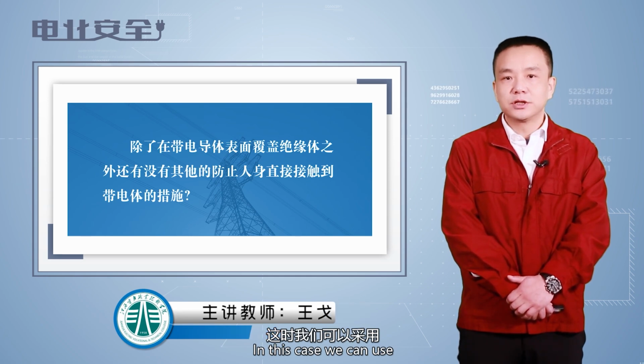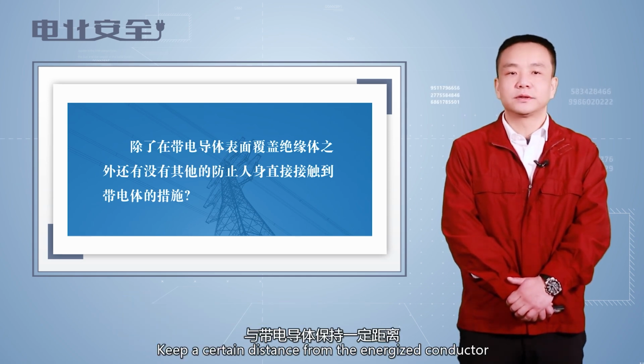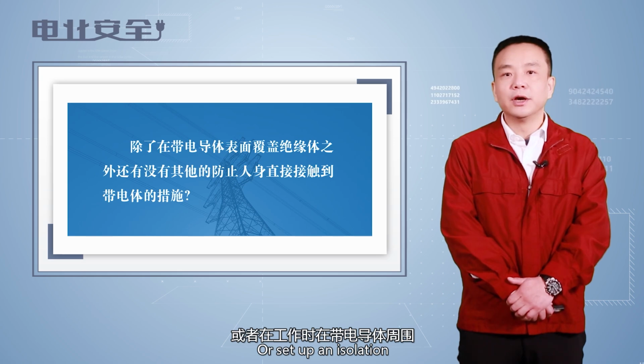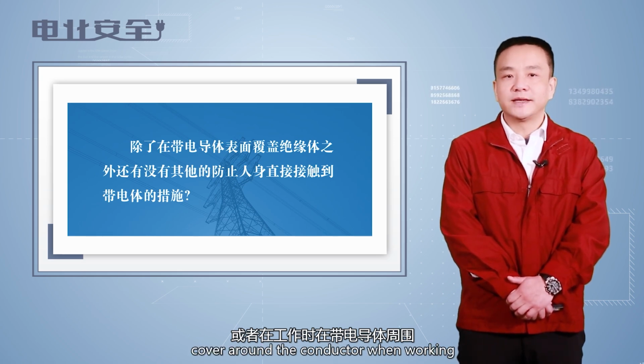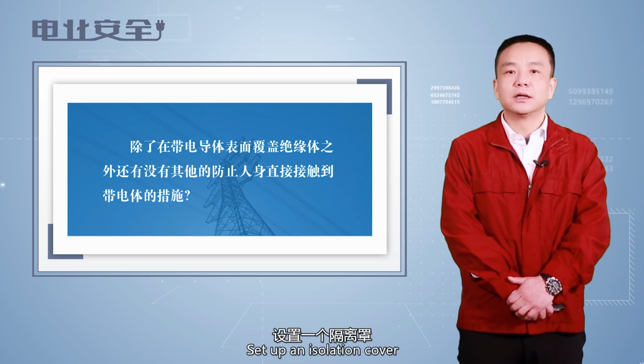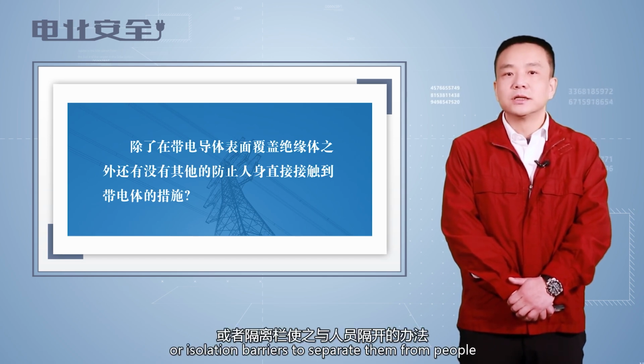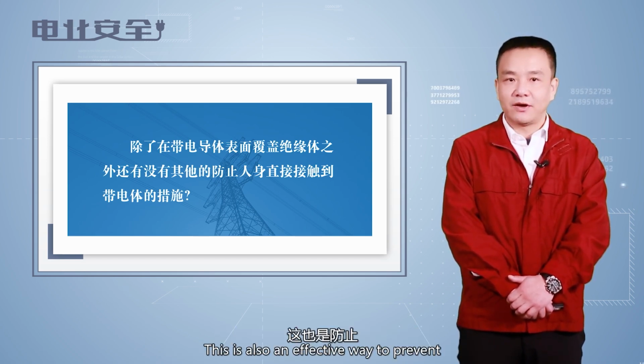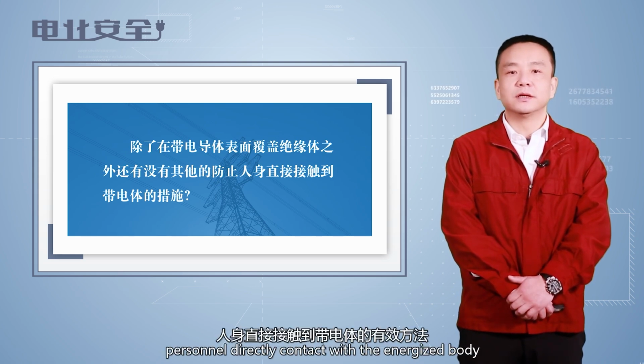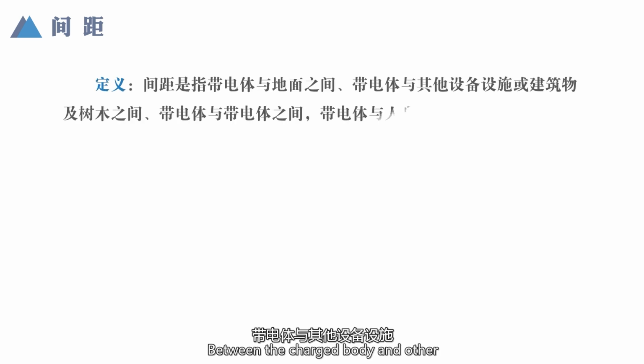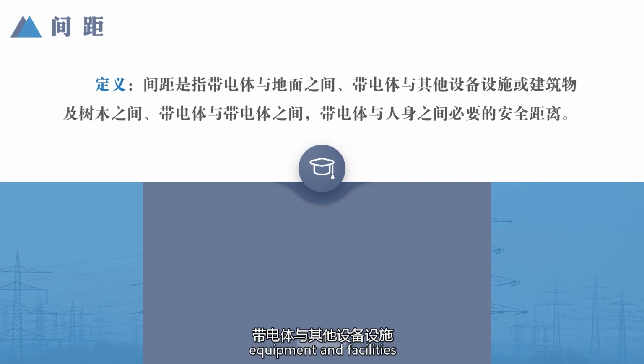In this case we can keep a certain distance from the energized conductor, or set up an isolation cover or isolation barriers around the conductor when working, to separate it from people. This is also an effective way to prevent personnel from directly contacting the energized body. First, look at the concept of distance. The distance is between the charged body and the ground, between the charged body and other equipment and facilities, or buildings and trees, between a live body and a live body.